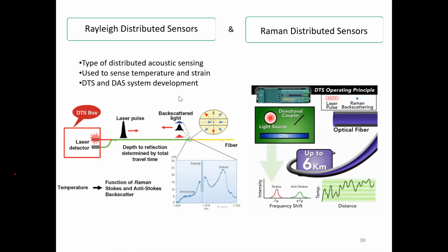So this is a very interesting property of light, that some light will always be reflected. Now, if anything happens to the optical fiber, the amount and properties of the reflected light will change. This change we can calibrate to get our temperature or pressure or whatever parameter we want to measure, right? So this is a very simple principle, but the light which is reflecting back is very, very feeble, with a very, very low intensity.